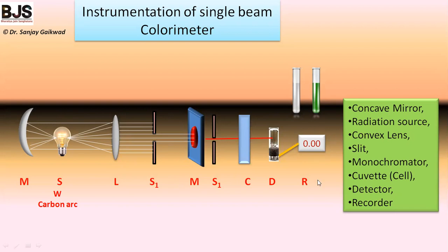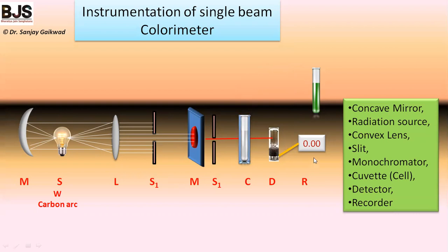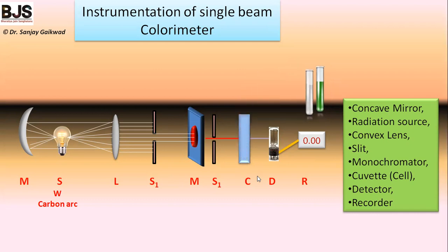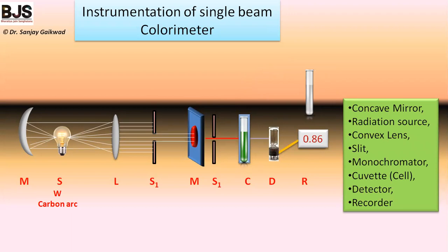In this instrument, first we place the blank solution in the cuvette and allow light to fall on the detector — this gives an absorbance equal to zero. When we replace the blank with a colored solution, light gets absorbed and we measure the absorbance, since the transmitted light decreases. Only the colored pigment is measured in terms of absorbance. This is the function of the colorimeter and it is used for determination of the concentration of an unknown solution.